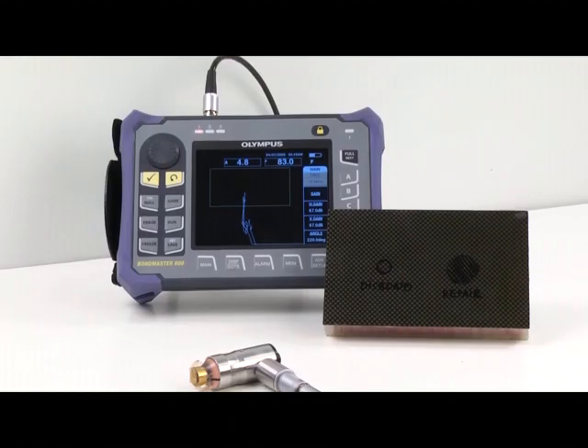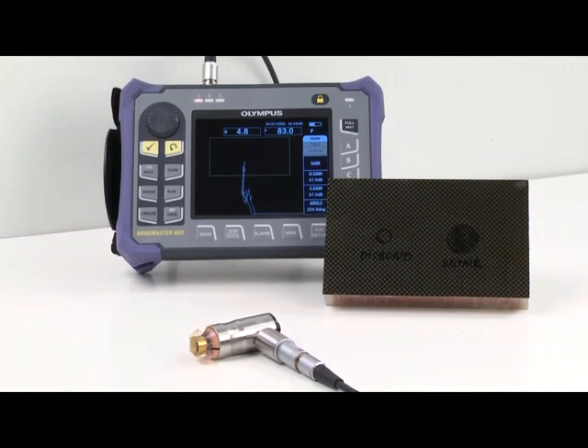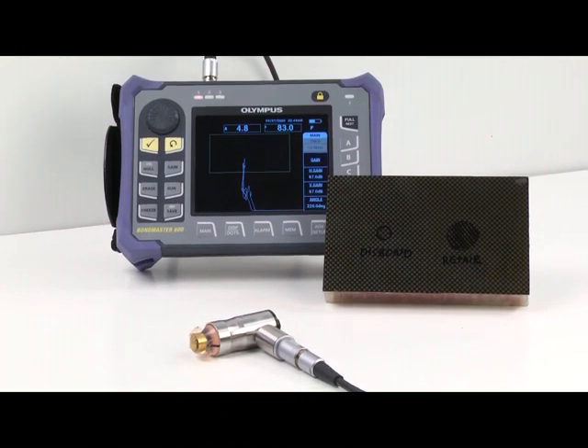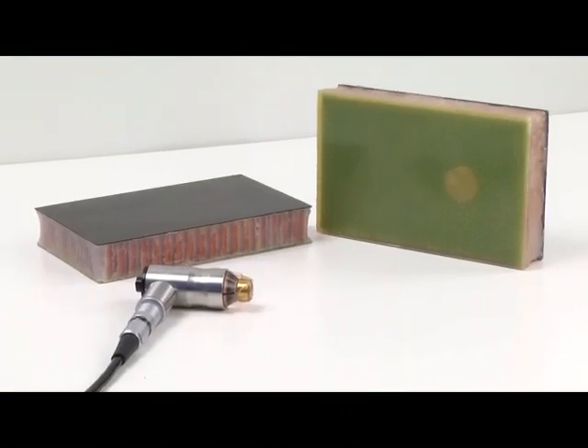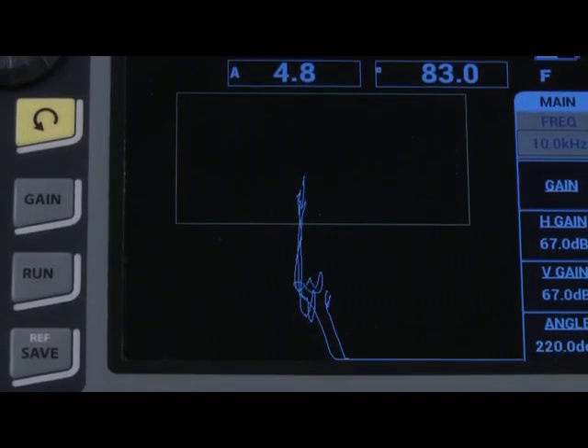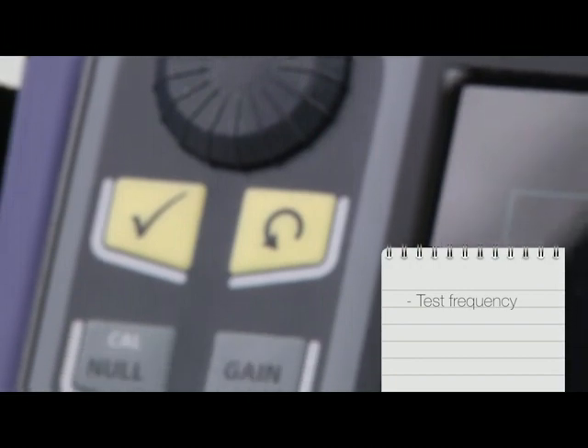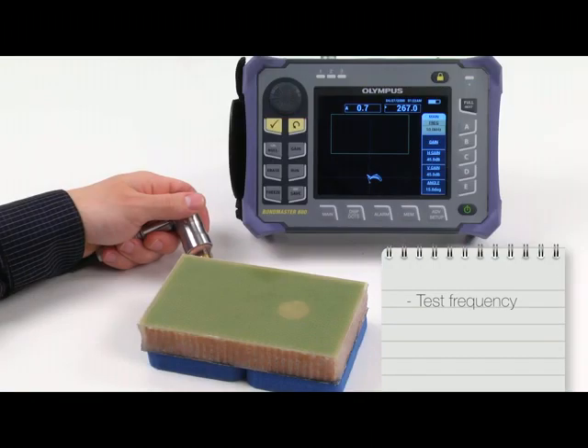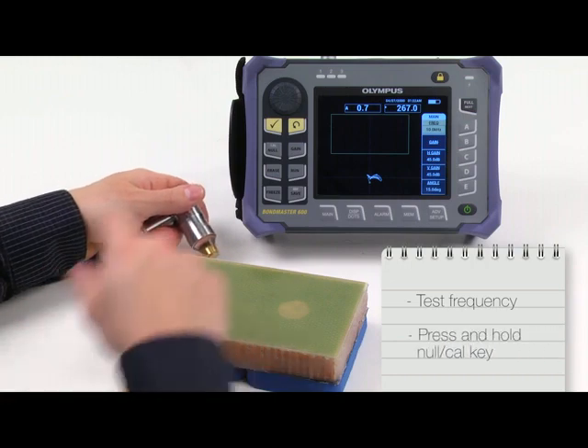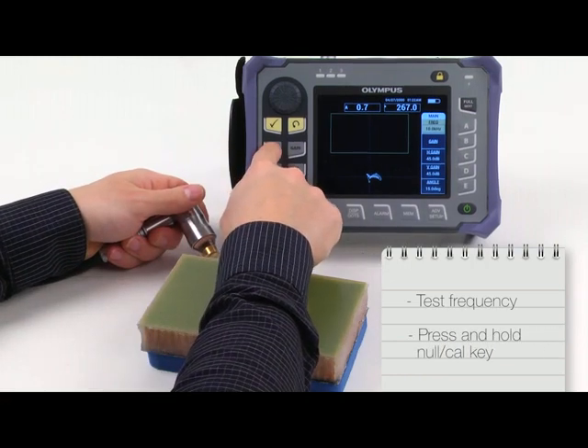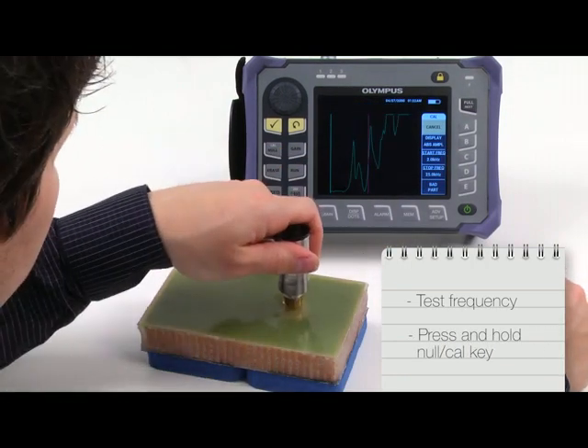Now we'll discuss how to define working parameters for inspecting honeycomb composite with the MIA mode. This section is targeted at users who write procedures or develop bond testing applications. The most critical parameter is the test frequency. Assuming you have a working MIA configuration, press and hold the null cal key to enter the frequency calibration mode.